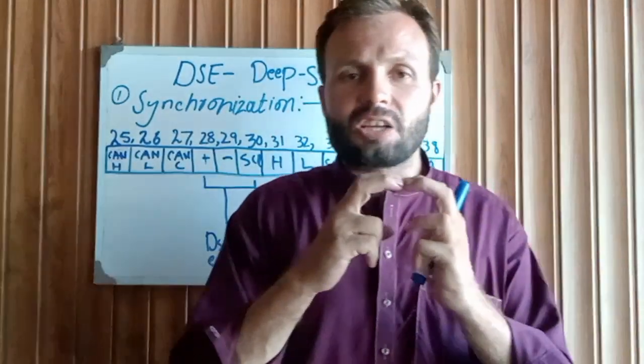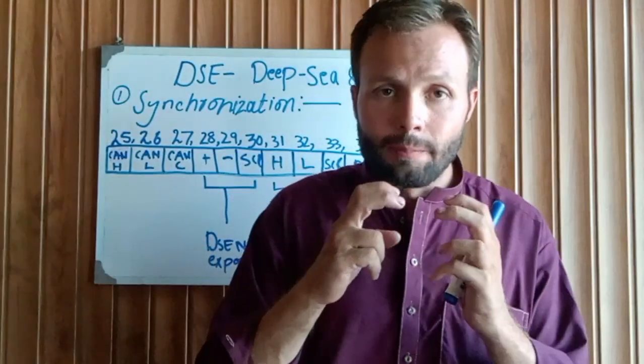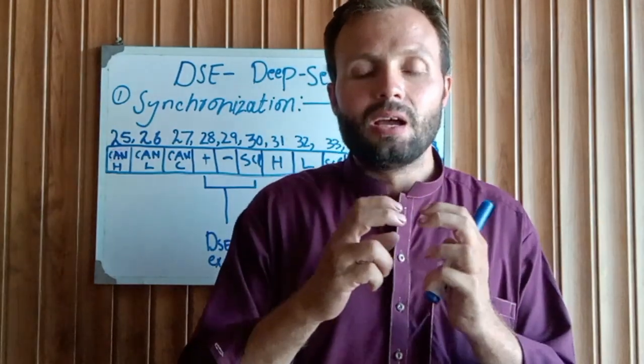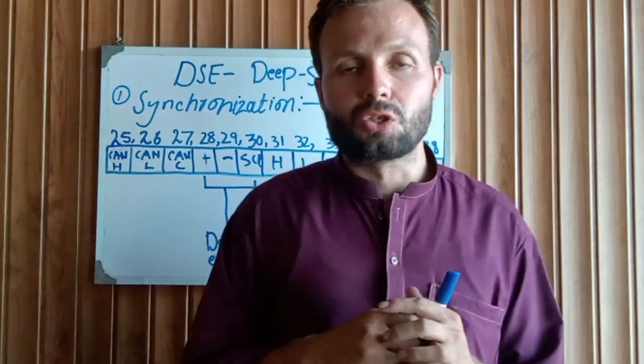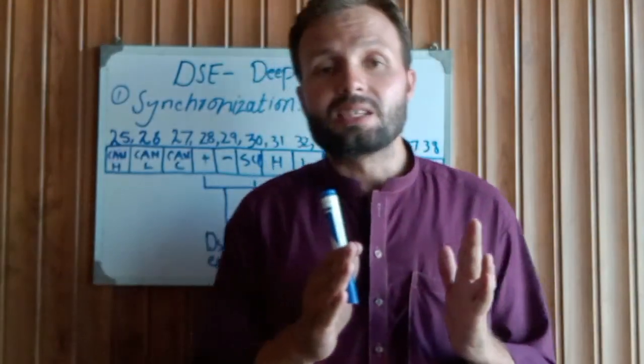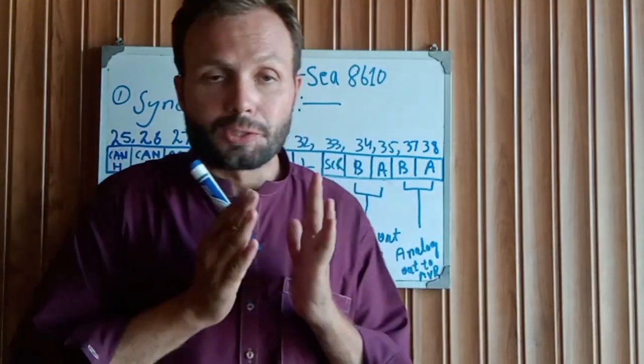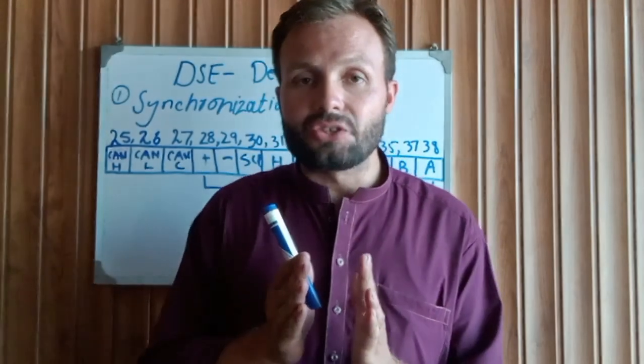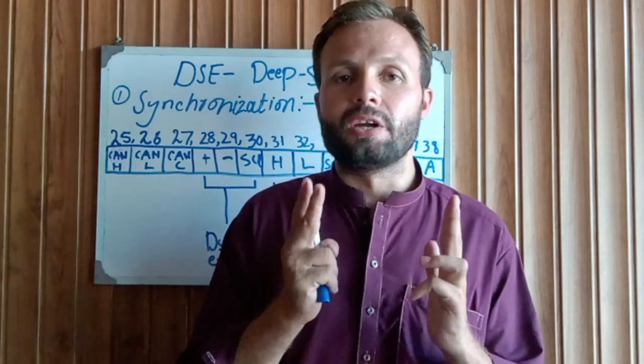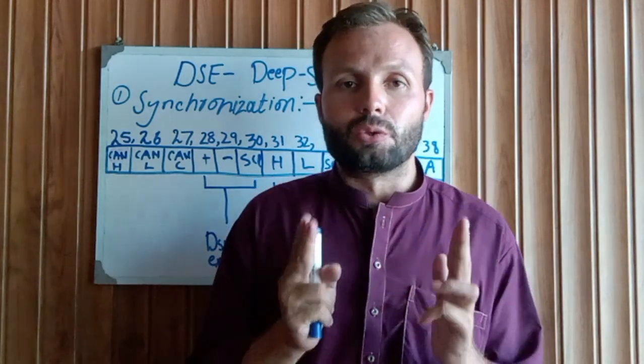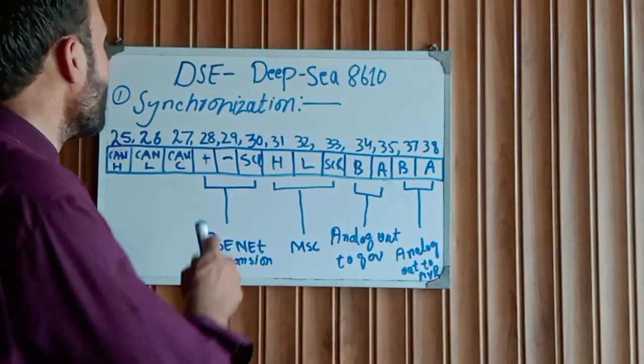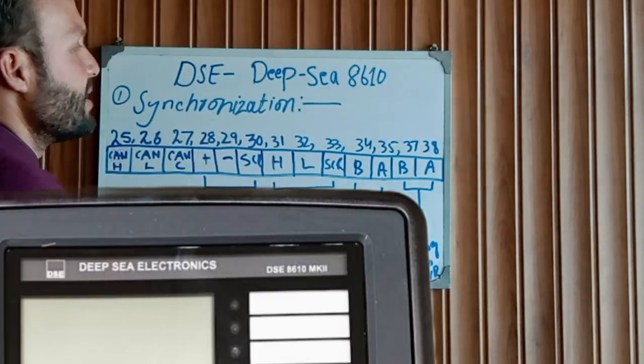Synchronization means two generators running with the same frequency, same voltages, and same RPMs. We need to adjust the frequency of both generators the same, and also the voltages and the governor system and the RPM. This DSE controller automatically controls the generator speed, generator voltage, and the governor system to synchronize two generators to each other.